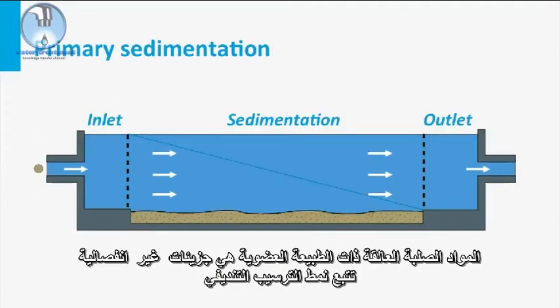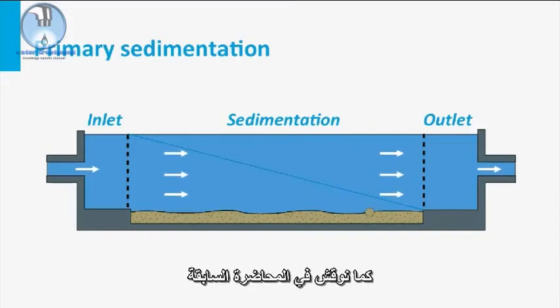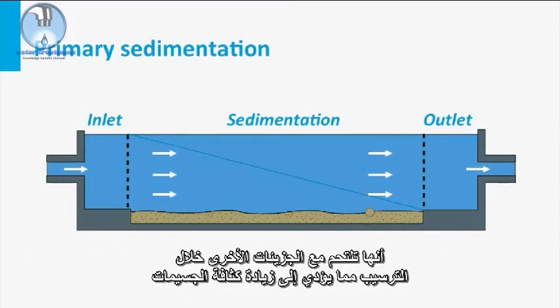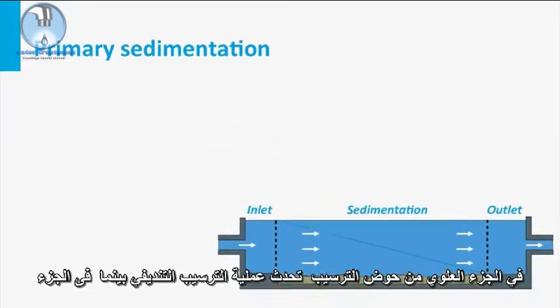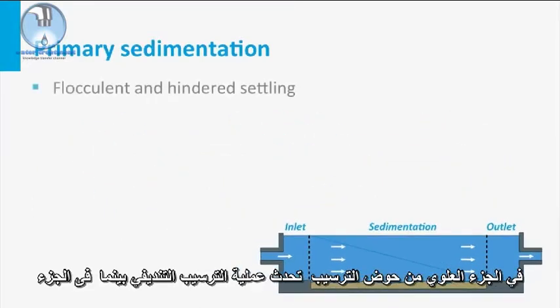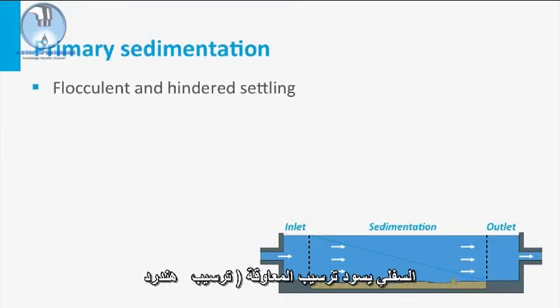Suspended solids of organic nature are non-discrete particles and follow the flocculent settling pattern as discussed in a previous lecture. They coalesce with other particles during settling, leading to increased particle density and thus increased settling velocity. At the upper part of the clarifier, the flocculent settling process occurs, whereas at the lower part, hindered settling is dominating.